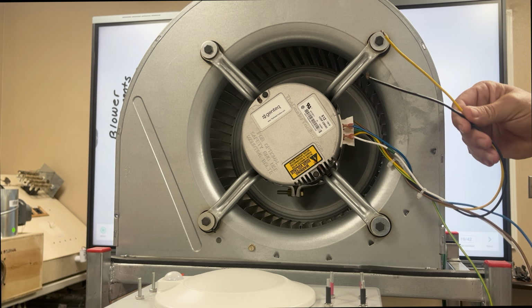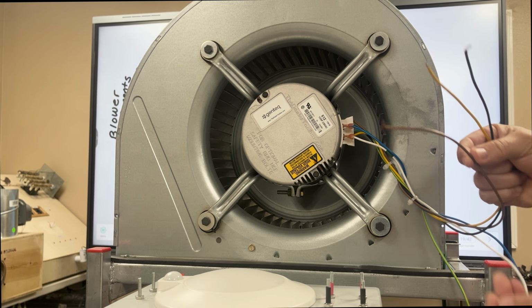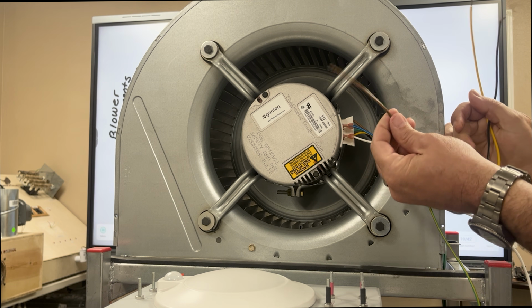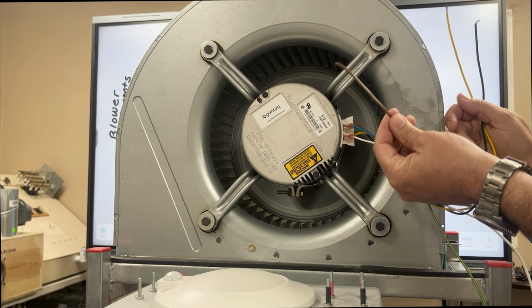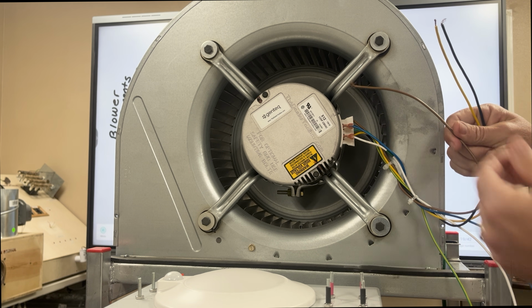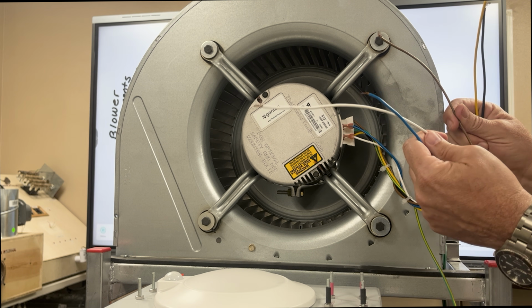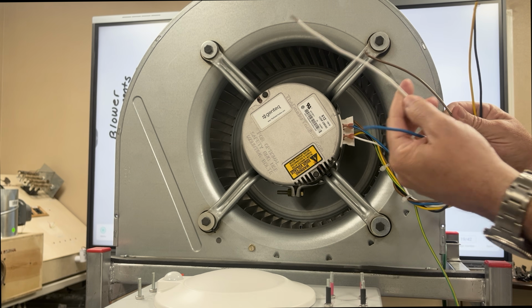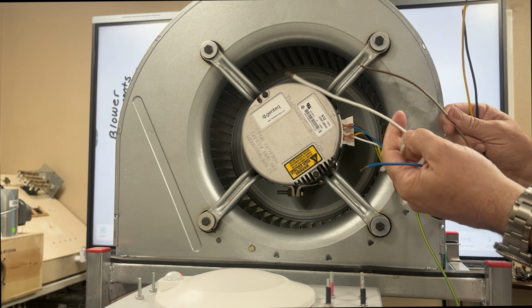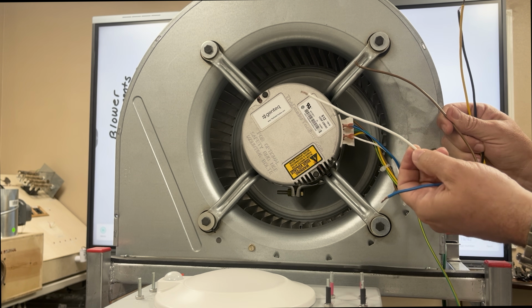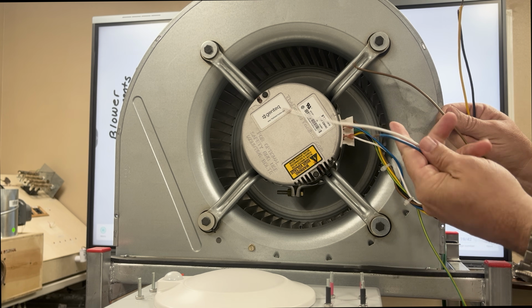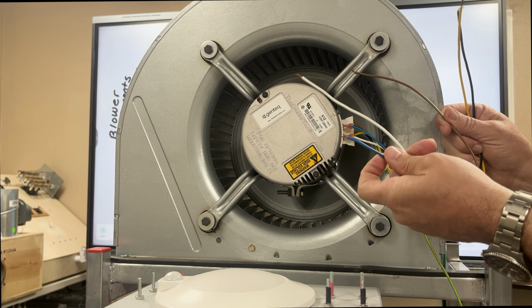And then we have brown, which is going to be common. All right, this is low voltage common, not high voltage common, okay? And then I have blue and white, which I can wire to 2 different speeds. Typically white is on a higher speed and blue is on a lower speed. That's how you'll typically find it in the field.